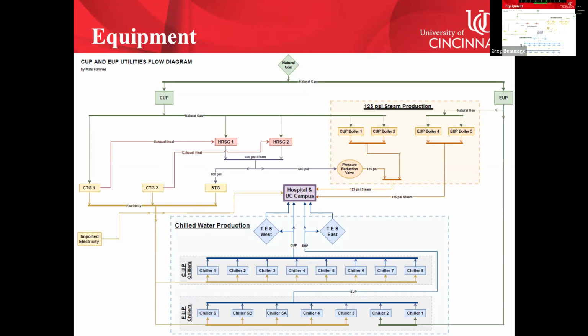What happens here, though, since we're a cogen plant, a combined heat and power plant, we capture that heat and recover it with our heat recovery steam generator, the HRSG, and that heat can be used in two different ways. We can either use that excess heat to generate high pressure steam and spin a steam turbine to generate more electricity, or just use that steam to heat the campus, in which case we don't have to run boilers, therefore we don't consume more natural gas, therefore less carbon emissions.